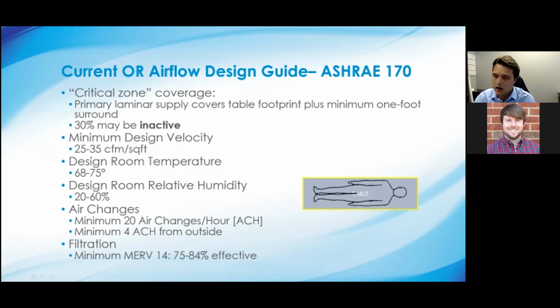So you have a critical zone here, and your primary supply of Group E non-aspirating, aka laminar diffusers, need to be above that space. However, when ASHRAE was writing this code, they understood that everybody else also wants to be as close to that table as possible. Everybody wants a piece of the action above that table. And so they said, all right, there's no way we can claim all of this space for ourselves. We need to give room for booms, lights, med gas, other people to get in there. And so they said, of that critical array, 30% of it may be inactive. Doesn't have to have a diffuser there. It can be a boom, a light, or whatever else you want. So you could drop this diffuser out and be perfectly fine from an ASHRAE standpoint.